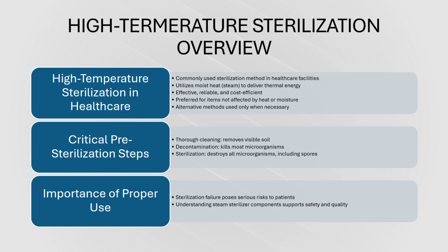However, this method is only suitable for devices that can tolerate heat or moisture. When items cannot withstand these conditions, we can use other methods to sterilize certain instrumentation. So remember that sterilization is only effective if items are properly cleaned and decontaminated beforehand. Cleaning eliminates visible debris, while decontamination reduces the microbial load, though not completely. So remember, cleaning and decontamination are two separate processes.